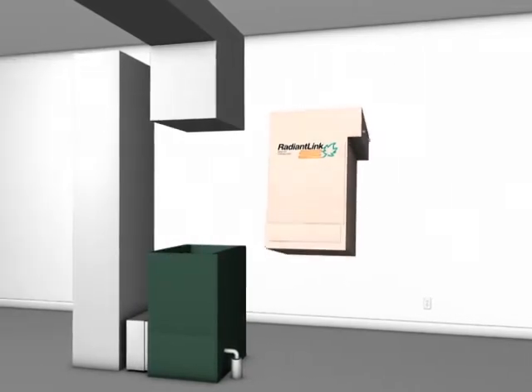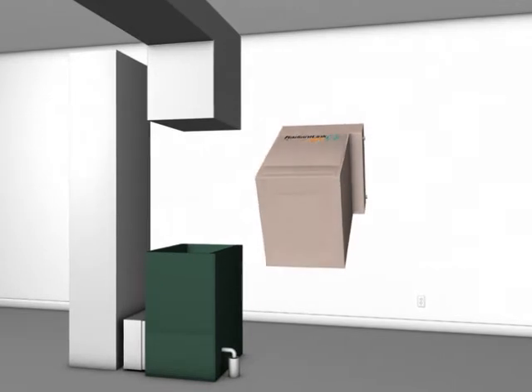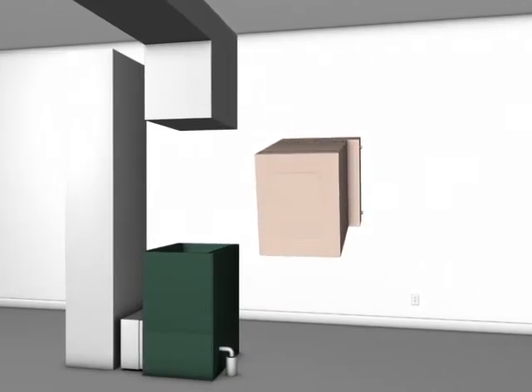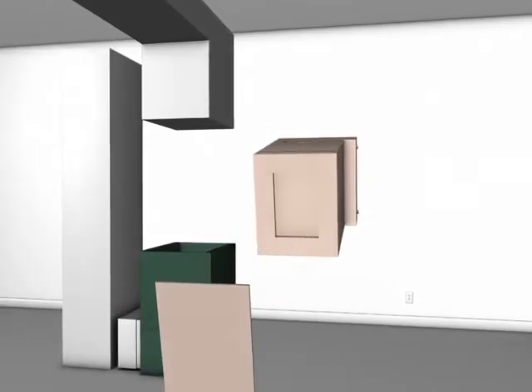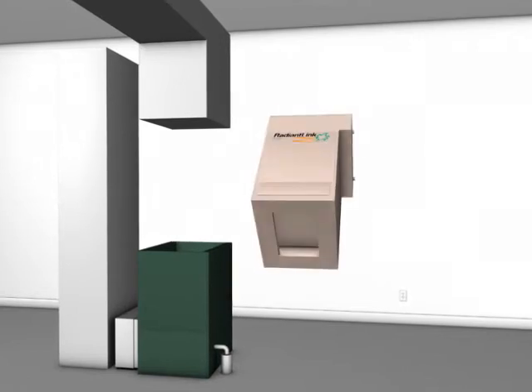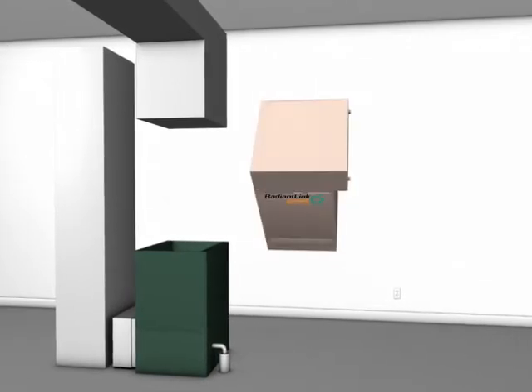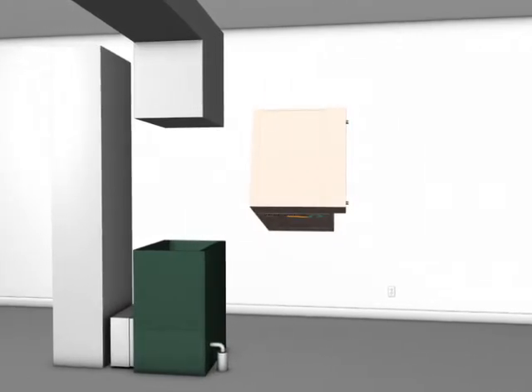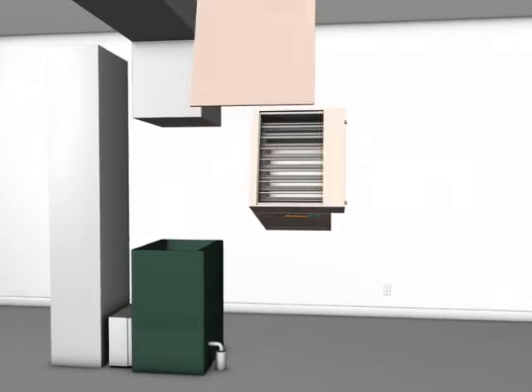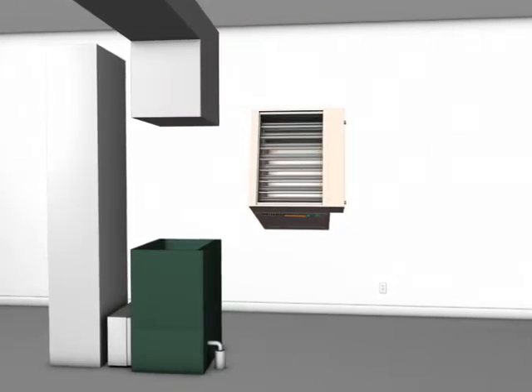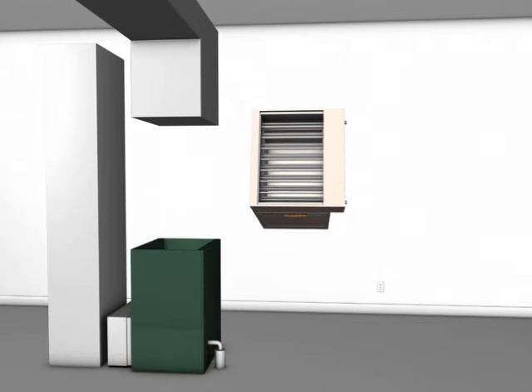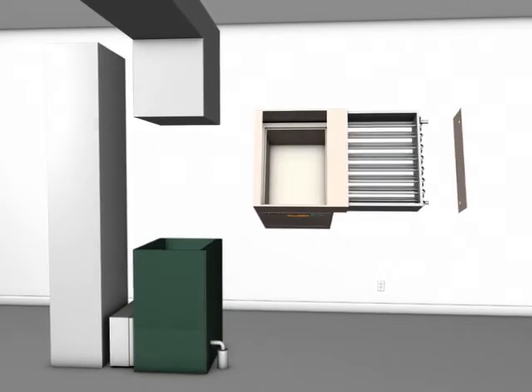Measure the furnace top supply air opening size and cut an opening to suit in the bottom of the plenum. Determine how the supply air ductwork will be configured to minimize airflow restrictions and cut a suitable opening in the top of the plenum. Be careful not to damage the coil within the plenum. The coil can be removed first if necessary.